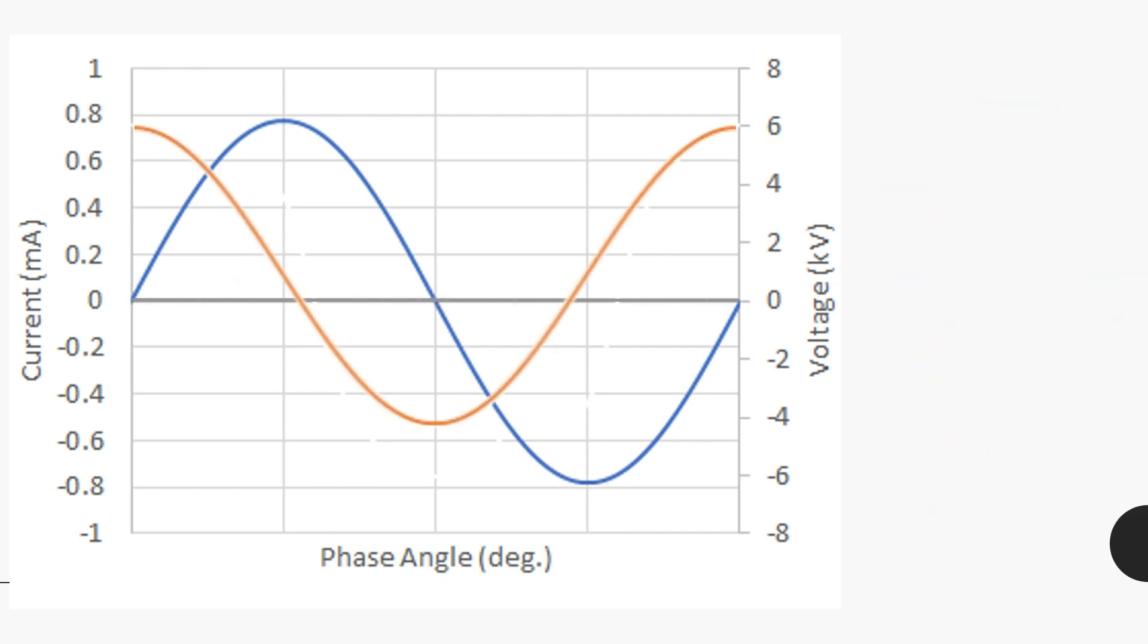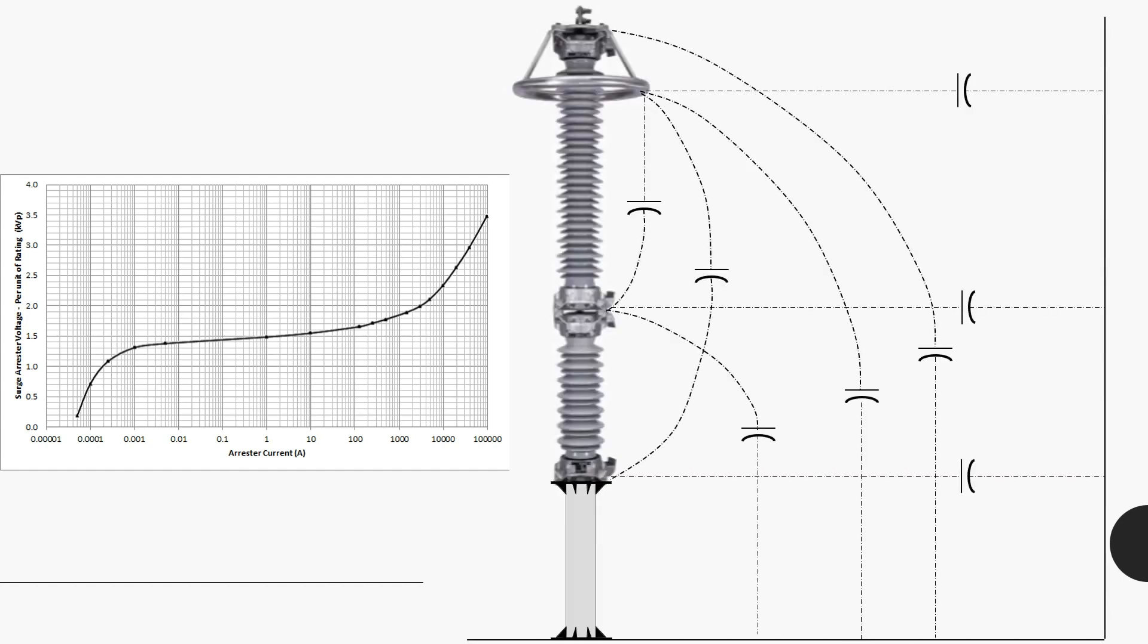The capacitive component of leakage current is not actively responsible for anything. The capacitive current is mainly because of the permittivity of non-linear metal oxide resistor as well as stray capacitance and grading capacitance of lightning arrester at site. There is no evidence that the capacitive component of leakage current would significantly change due to the change in VI characteristics of the non-linear metal oxide resistors.